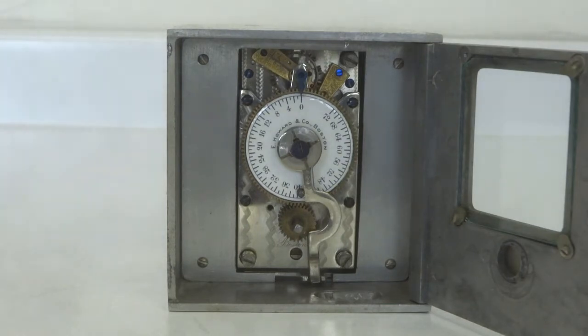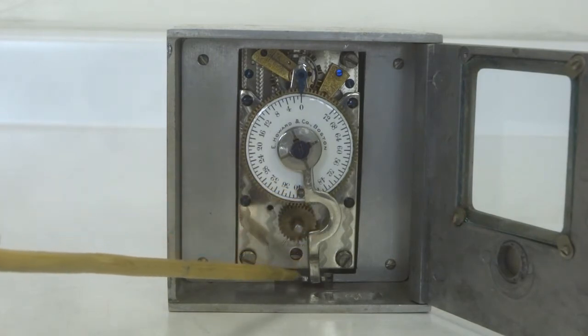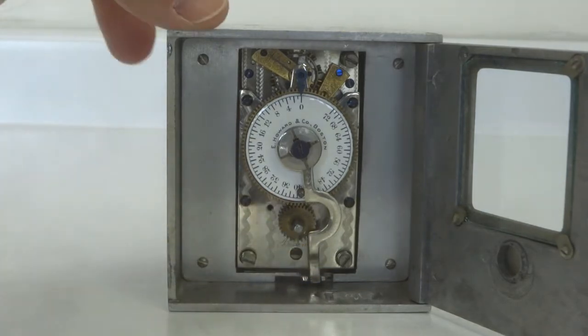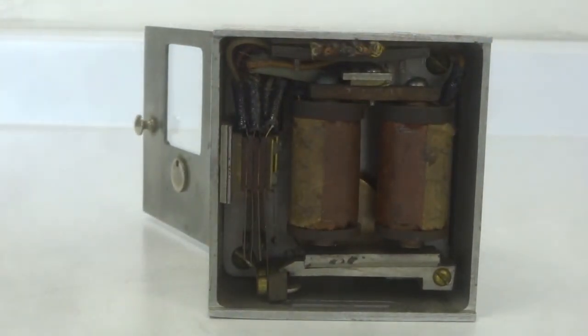What you will see here is an armature which is abutting the pin on this dial. Right now it is all the way wound down to zero, and this armature is pushing a spring-loaded piece all the way to the right. That piece is connected to this electrical piece here, which is then able to move either forward or backward according to the movement of that armature, thus allowing these contacts to either be opened or closed.